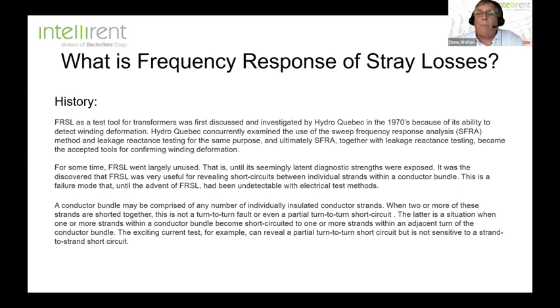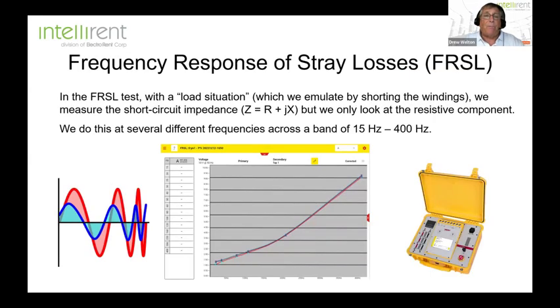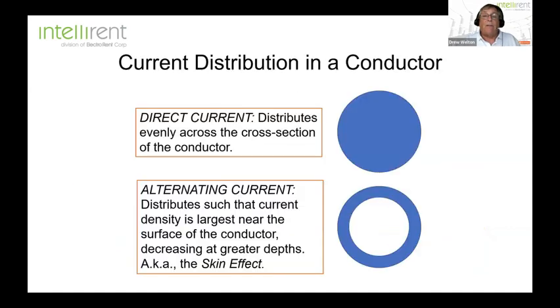What they were doing was taking the frequency and running it up to 400 hertz and measuring not just the entire impedance, but just the resistive value that they were seeing at these higher frequencies. And they do this between phases. And what they were seeing is pretty interesting: where we're looking for mechanical failures with leakage reactance, with frequency response of stray losses we're looking for a possible electrical failure with what's called a shorted conductor bundle. Now, this is done again just measuring the resistance of the impedance per phase on each of the three phases. So what happens when we apply a higher frequency?